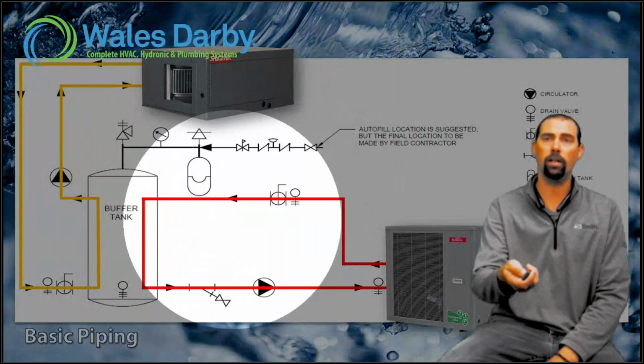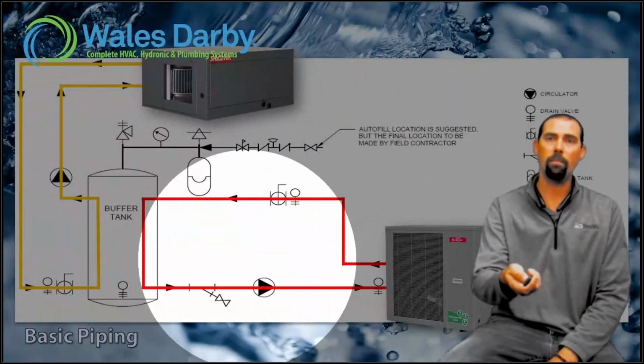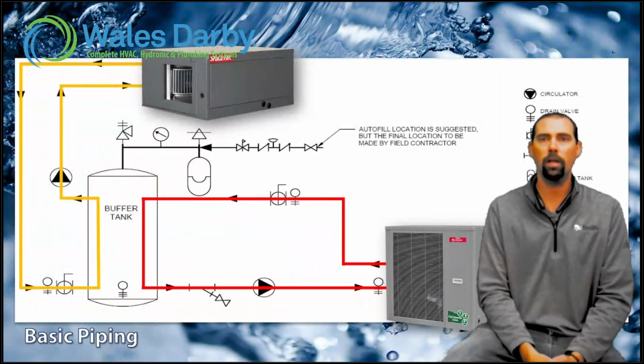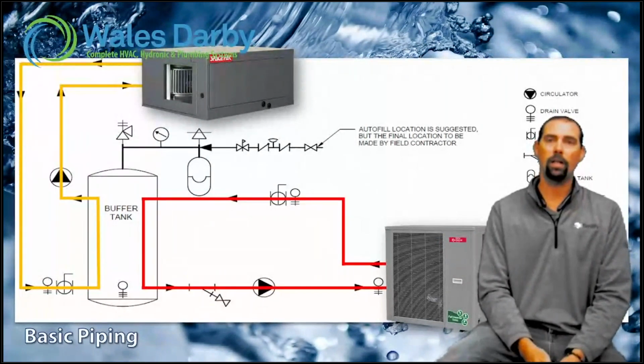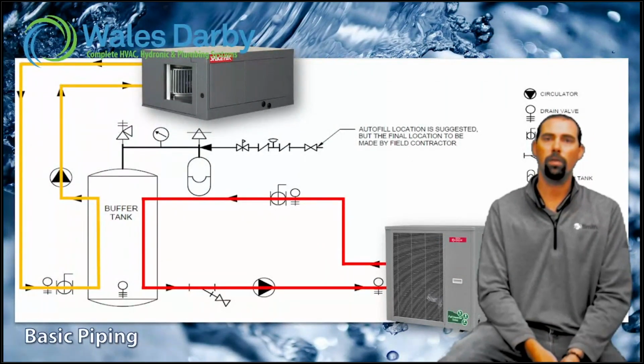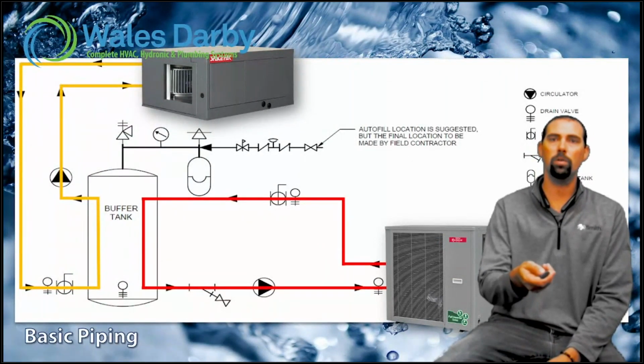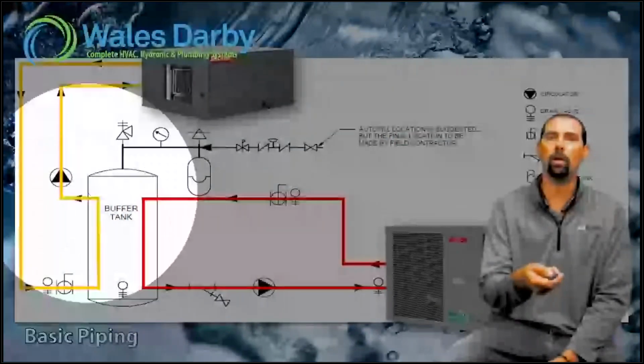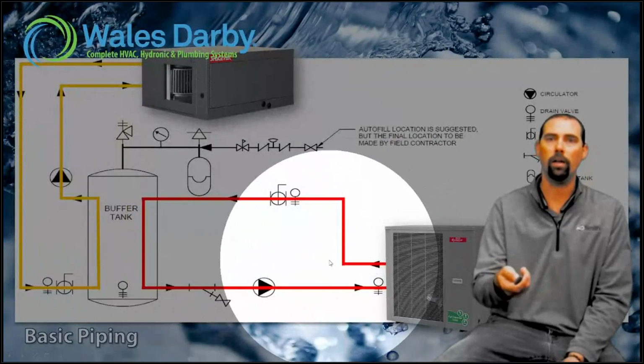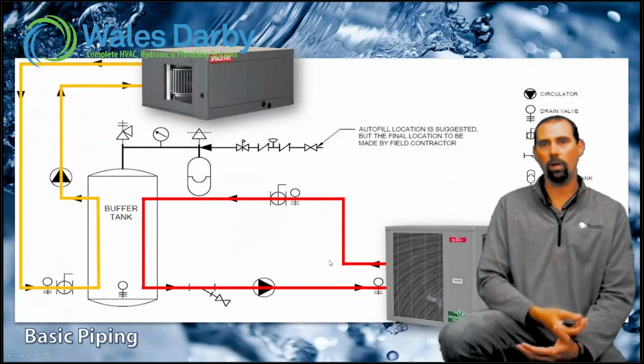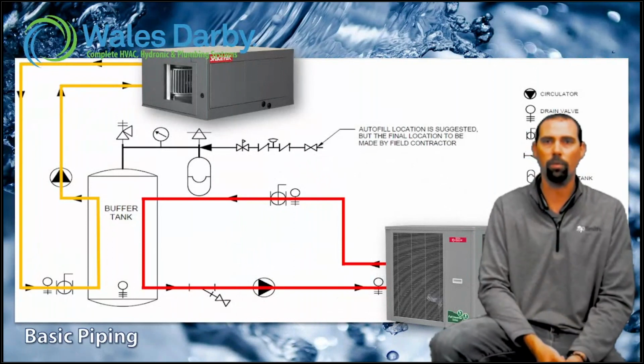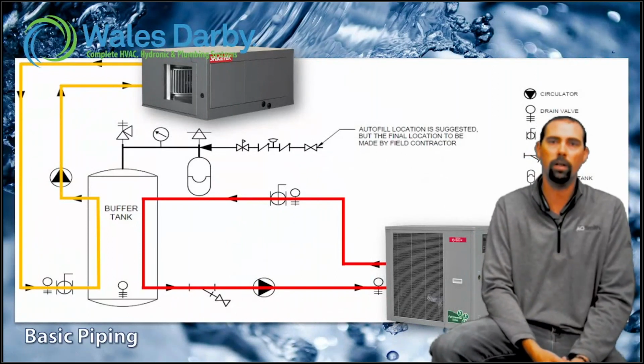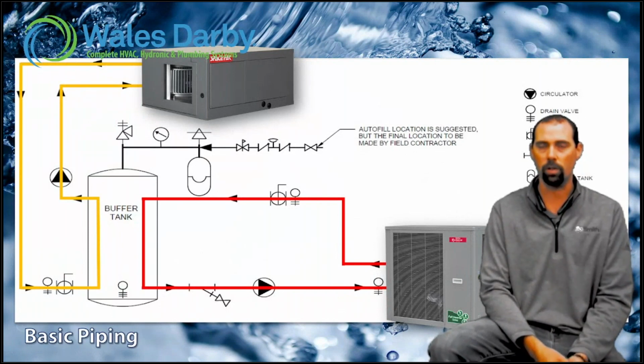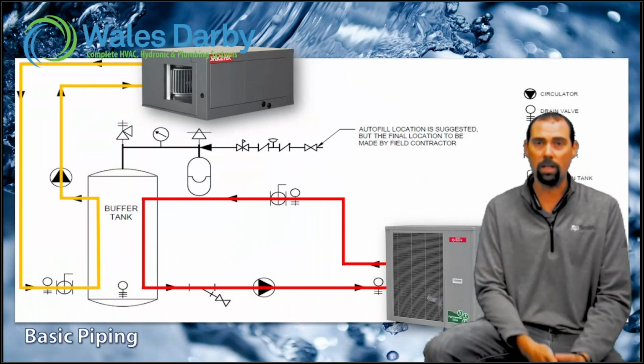That inverter side, the heat pump side, the red piping, I might be flowing 10 GPM through there. I might have a radiant zone calling that's only giving me 2 or 3 GPM. So I can pull the 2 to 3 GPM out of this tank while flowing 10 on the other side. It's one of those things, just like a hydraulic separator - the buffer tank's just a little bit bigger, and it adds the storage feature. We keep those BTUs in there.